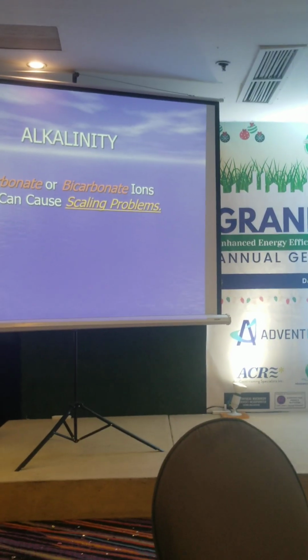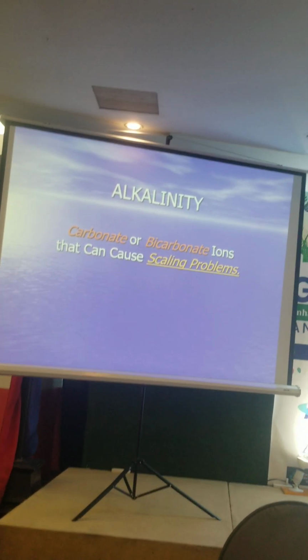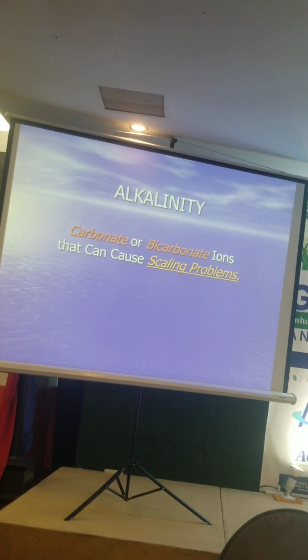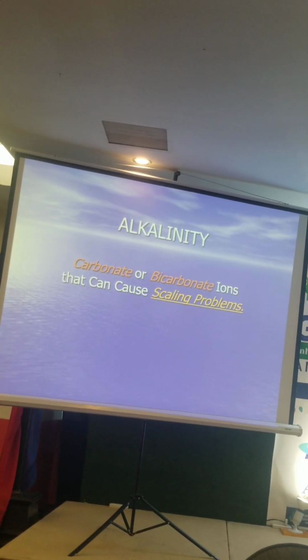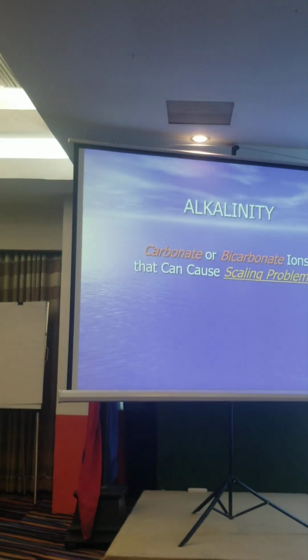Alkalinity comes from carbonates or bicarbonates, also hydroxyl. There is hydroxyl alkalinity in the boiler, but in the cooling tower, there are only two types of alkalinity: carbonates and bicarbonates. This will cause scaling.